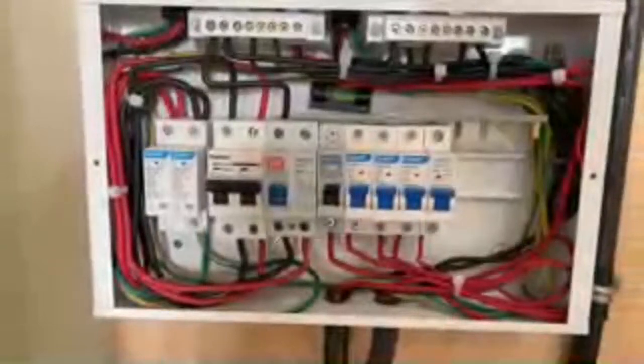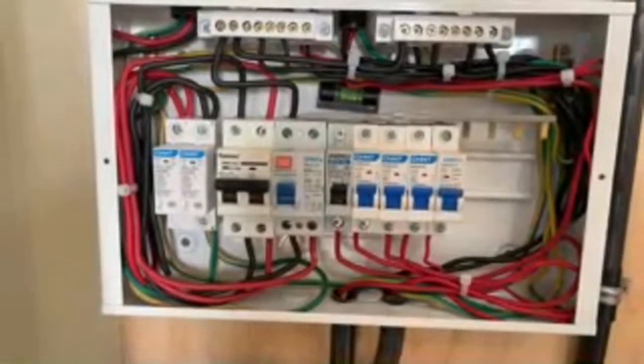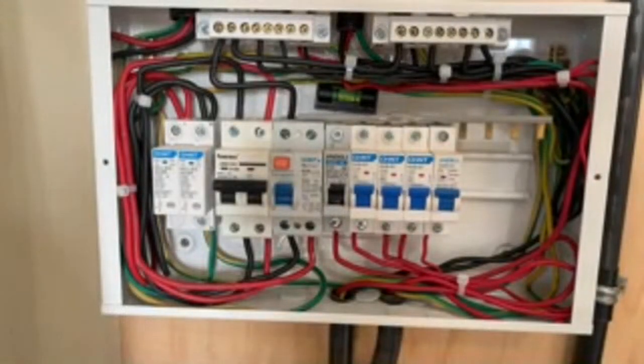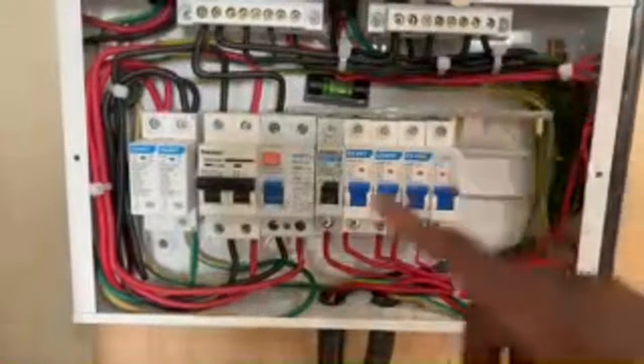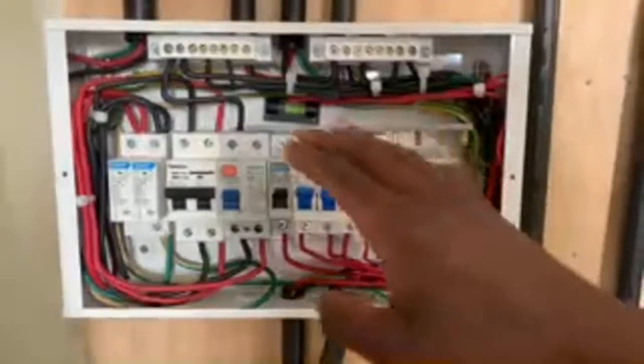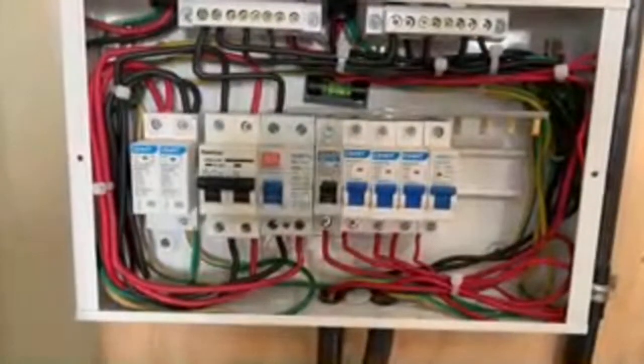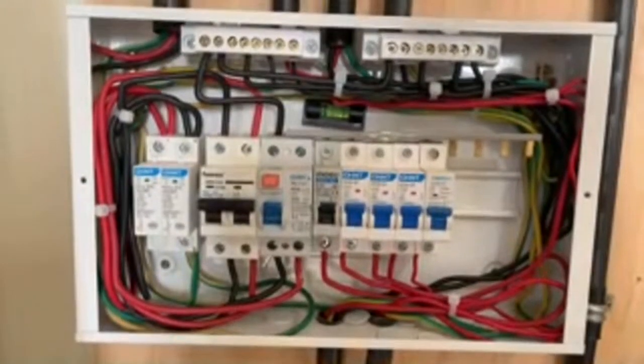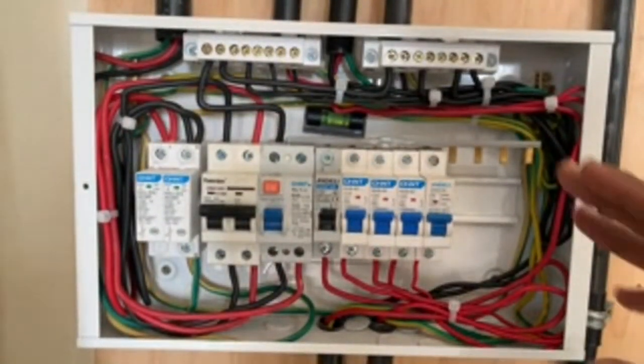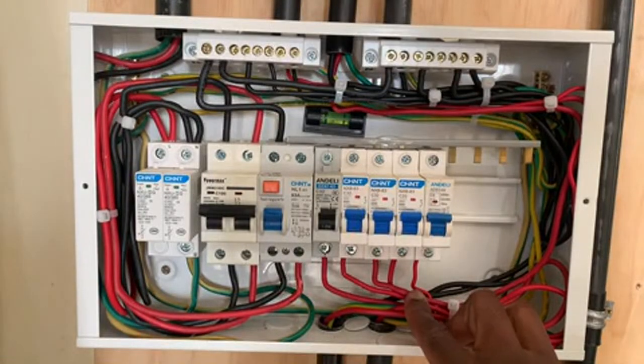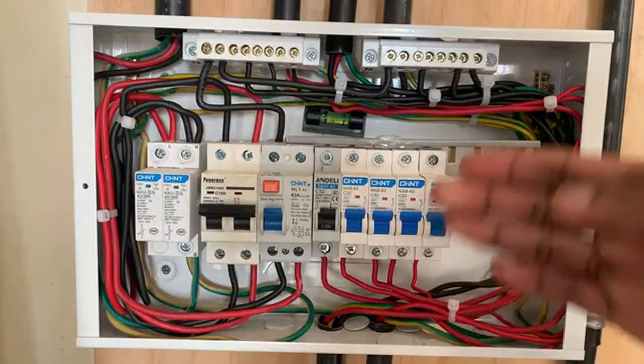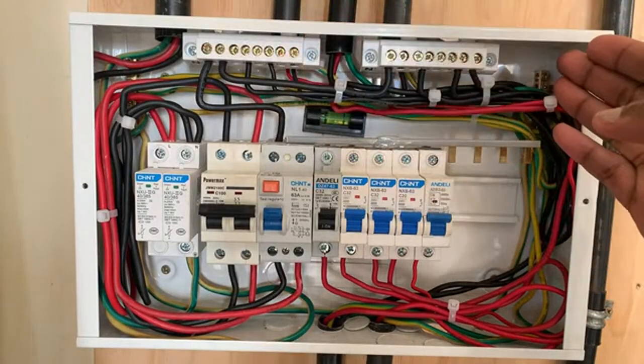And I did a very great wiring of it, as well as an explanation which you can easily access and find a lot of value. We have the earth bars here. I have 2 of them on the sides there, as well as here. I also have 2 neutral bars that are very, very important in this entire setup. Now we are talking about this. The size of the wire that comes from the MCBs should be the same as the size of the wires coming from the neutral bars as well as the earth bars.